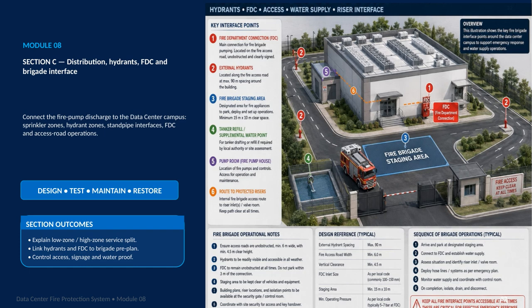A major theme is coordination. Hydrant locations, FDC access, signage, and access roads all need to support fast, reliable response. The water supply must also be controlled and documented through testing and proof of performance. The operating mindset for this module is simple: design, test, maintain, and restore. These 4 actions help keep the distribution system ready before an incident, functional during one, and dependable afterward.